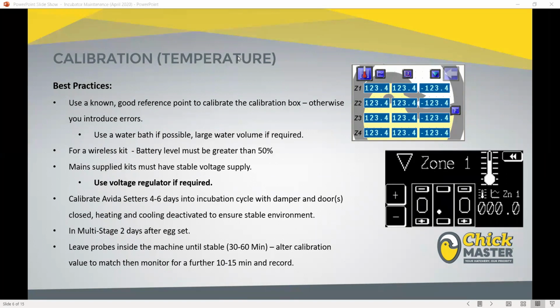Now, the reason we use a reasonably large body of water is for stability. The last thing you want is fluctuations in that temperature whilst you're trying to validate those readings. Because what you'll often find is your mercury thermometer is going to change temperature exceedingly quickly within a couple of seconds, whereas the probe on your calibration box may take several minutes for it to stabilize at a new temperature. And with any changes in temperature, what you're looking for is both probes following that temperature trend at the same time.